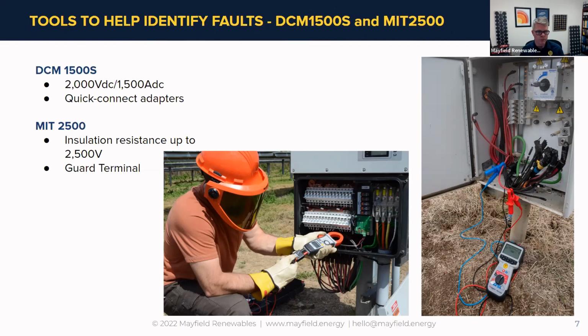One of the big unique things on this tool is that it goes up to 2.5 kV. You can adjust it manually anywhere, I think from 50 volts to 2,500 volts. Is that right, Mike? Yes. And you can dial in, so you could say a 1,500 volt insulation resistance test if you want. It also has a guard terminal, which I'll let Mike speak to so I don't do it any injustice.